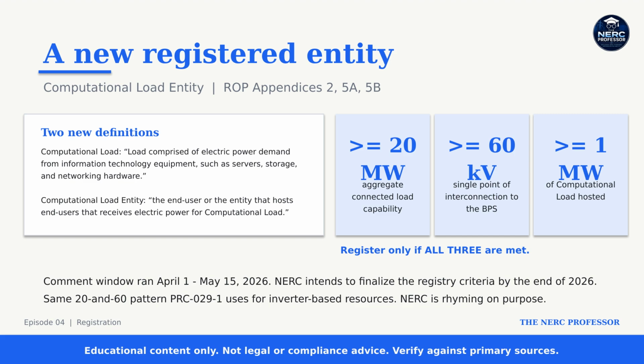3 thresholds, and you must meet all 3. 20 megawatts or more of aggregate connected load capability, a single point of interconnection to the bulk power system at 60 kilovolts or above, and 1 megawatt or more of computational load. If 20 and 60 sound familiar, they should. That is the same numeric pattern PRC-029-1 uses for inverter-based resources with megawatts in place of MVA. NERC is rhyming on purpose.